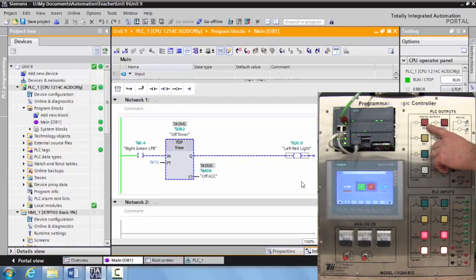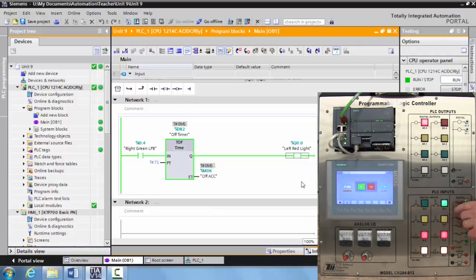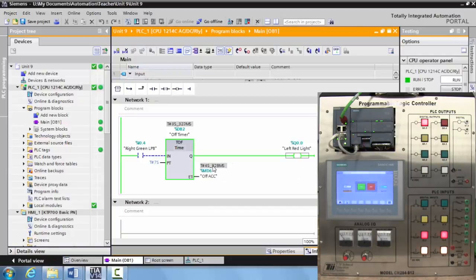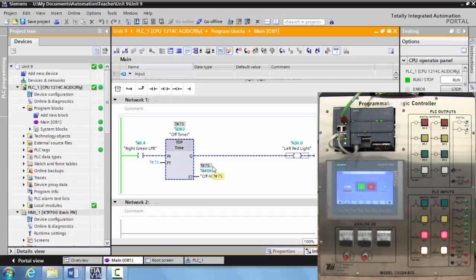You will see this red light go true as soon as I activate the button. And now it's on. The output is on and it's operating whatever it is — a cylinder, a motor, a pilot light. Now how the off delay works is exactly what it says: it delays the off. So when you deactivate the latching push button, the timer will run for seven seconds and then turn off. We can leave it on for ten minutes, three days, whatever is needed. But right when you deactivate the switch, the light will be on for whatever that preset time is.